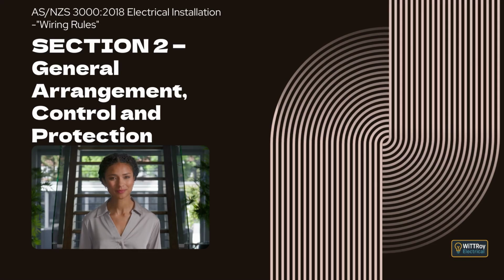Clause 2.5.4.3, position of devices for short-circuit protection, explains that, under normal conditions, a short-circuit protective device must be installed at the origin of every circuit and at any point where the conductor size is reduced. This ensures that smaller conductors downstream are protected against high fault currents. The clause also allows for specific exceptions where the device may be installed in a different position or omitted, subject to conditions explained later in the standard.